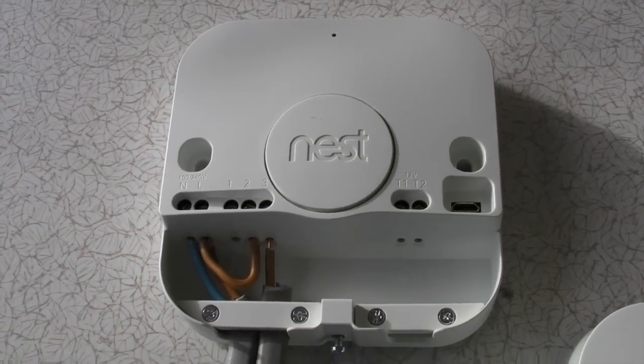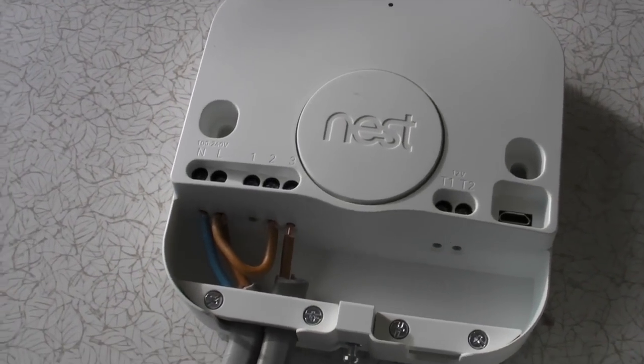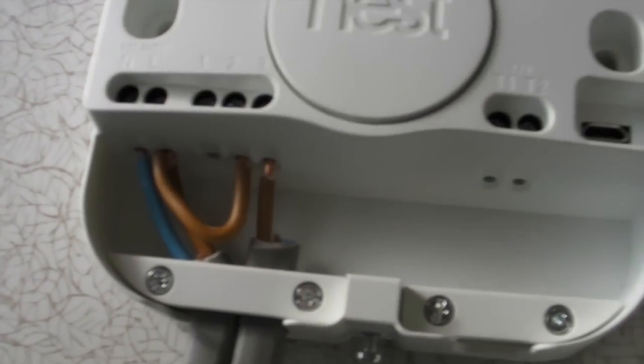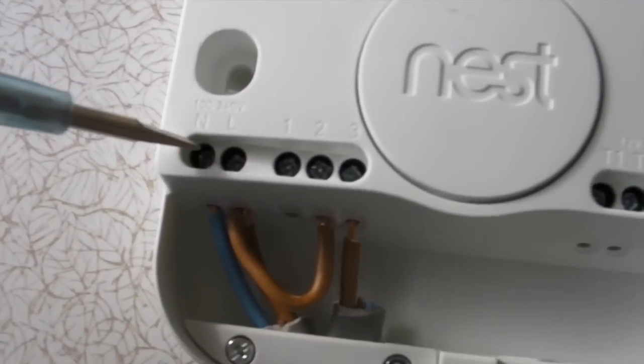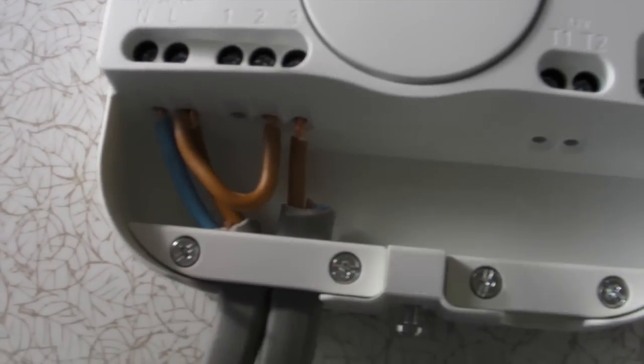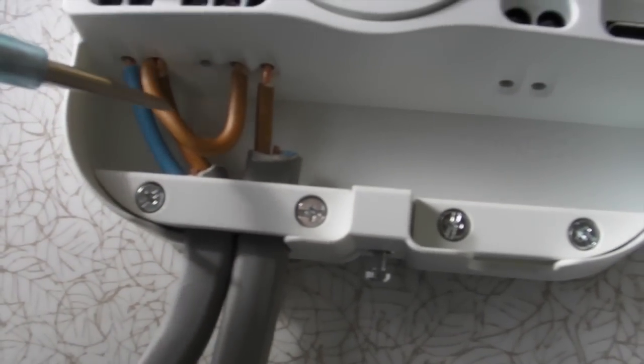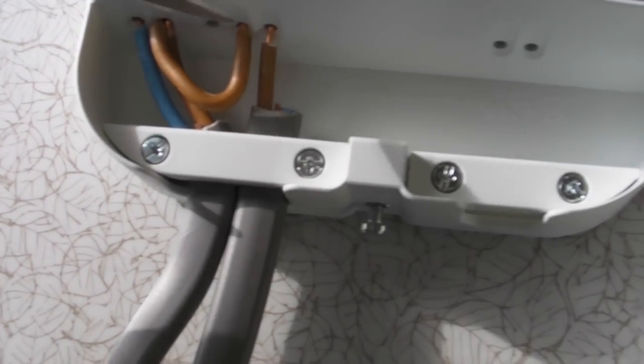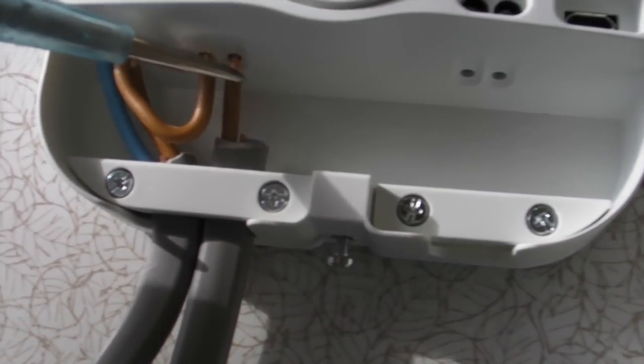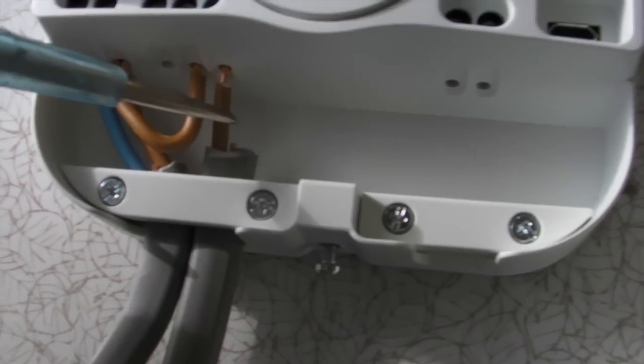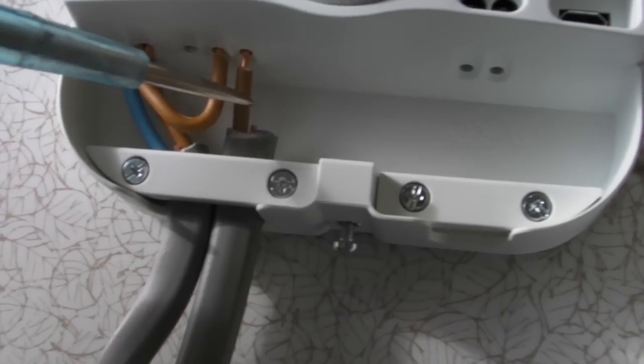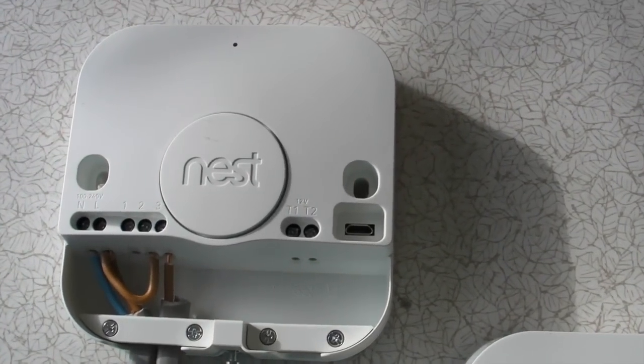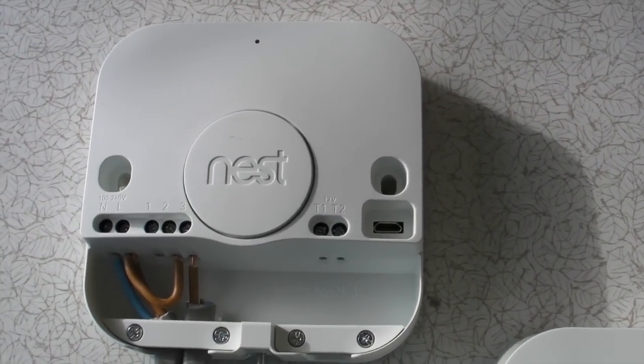Here's the wiring on the Nest box. Now I don't know if you can see this, so what I've done is I've just put a couple of tails on this, makes it a bit easier when you go to wire it in. So you can see the number, you've got neutral there, and then you've got your live. But what you do at the live, you put a little bridge wire in and that goes into number two, that feeds that, and then you have another wire there. Now this is your main output back into that white wire I was showing you in the controller. Now that all gets wired into that box, so it's got to be easy to cut the wire tails on this thing, then go to the junction box and wire it in. So I'll show you my wiring it in at the junction box.